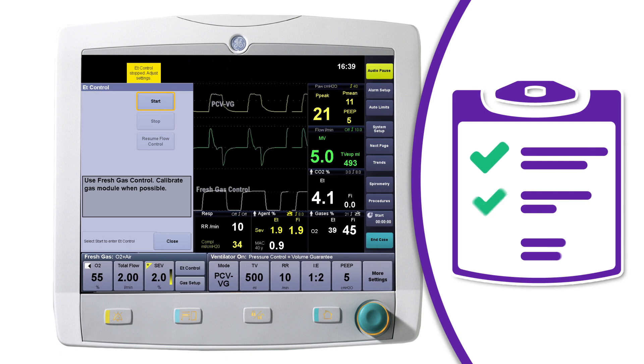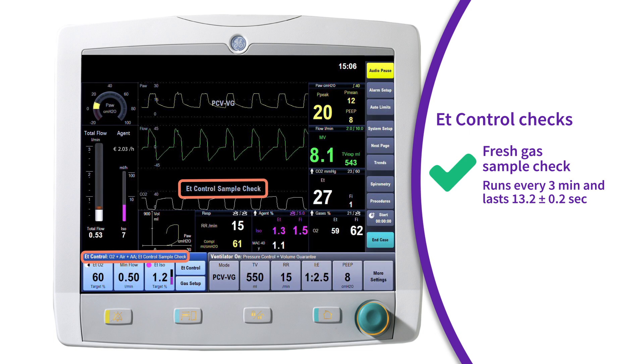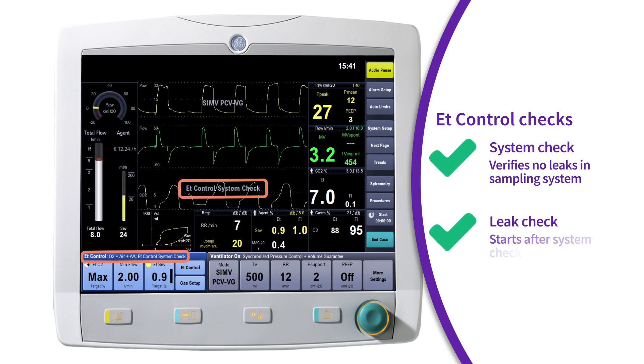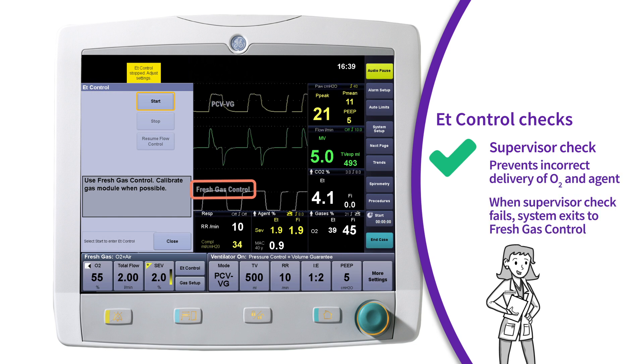Additionally, there are checks that occur before end-tidal control begins and will continue to run while in ET control. The end-tidal control fresh gas sample check guards against incorrect delivery due to faulty airway module readings. The end-tidal control system check and the end-tidal control leak check guard against incorrect delivery due to sample line issues, such as leaks. Lastly, the end-tidal control supervisor is an additional safeguard to ensure the system is able to control gas and agent delivery to meet the targets.